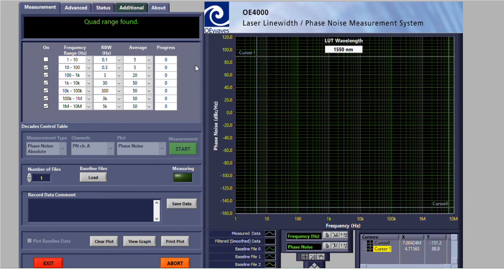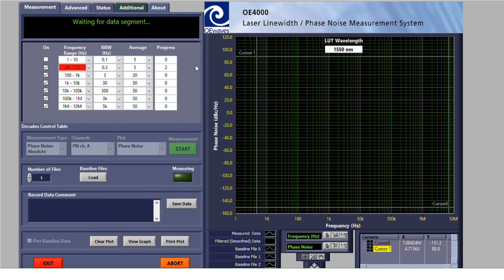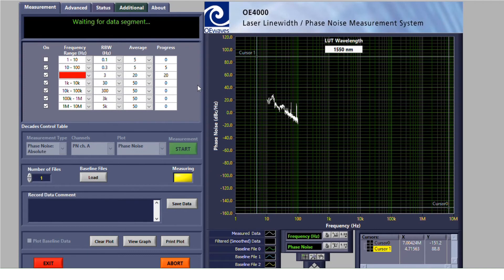Once this is achieved, the system will start collecting data. This is done a decade at a time and is indicated by the red blinking area at the frequency range column. At the same time, one can see the progress in the right column, which indicates how many samples were taken so far relative to the number of averages. When a decade measurement is completed, the data will be presented in the plot and the system will proceed to measure the next decade.